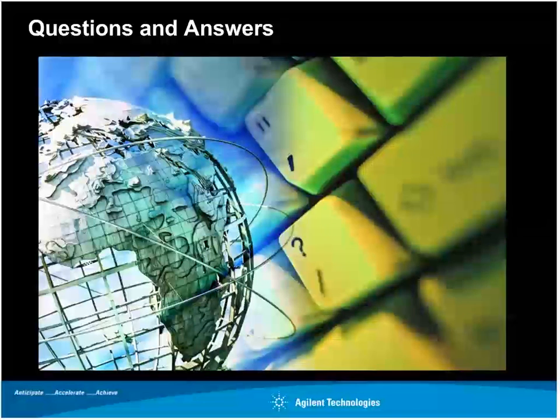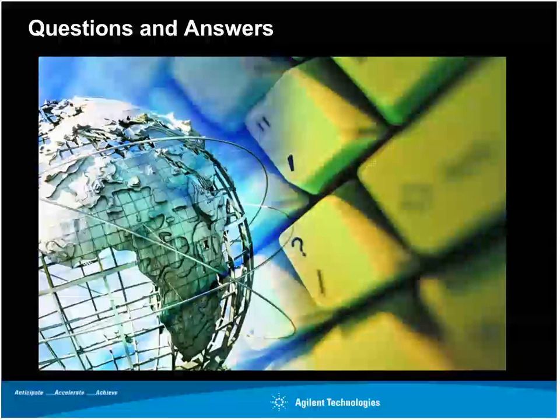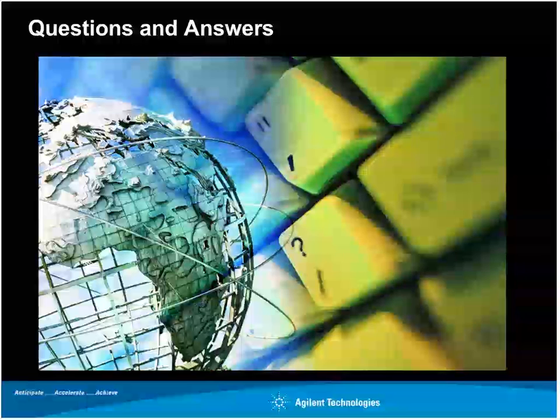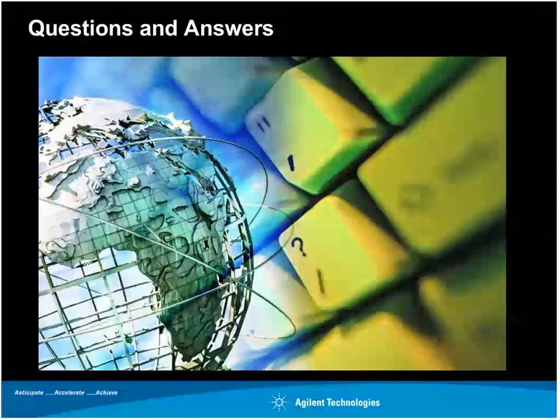Yeah, well, we did try to address that. The front page may look nearly identical between two different calibration laboratories, but it's really only by going back and looking at the actual specifics in the schedule of accreditation. That's where you really find out what these laboratories can do, what an assessor has taken a look at, made sure that the people have the proper skill, looked at the test laboratory standards that they have, and therefore made a determination of what is the best measurement capability and the corresponding measurement uncertainty that they can provide.